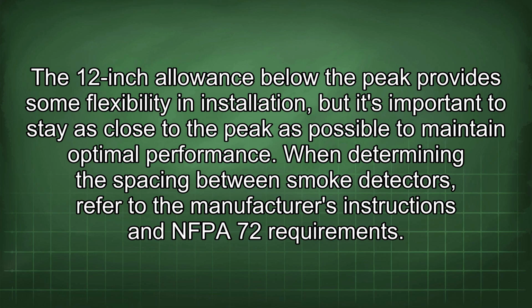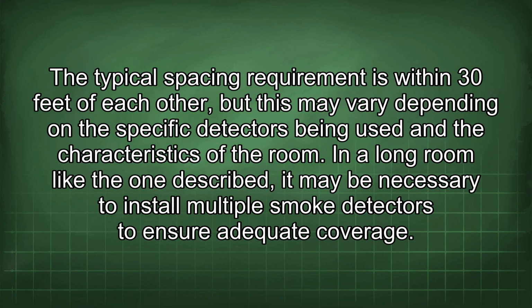When determining the spacing between smoke detectors, refer to the manufacturer's instructions and NFPA 72 requirements. The typical spacing requirement is within 30 feet of each other, but this may vary depending on the specific detectors being used and the characteristics of the room. In a long room like the one described, it may be necessary to install multiple smoke detectors to ensure adequate coverage.